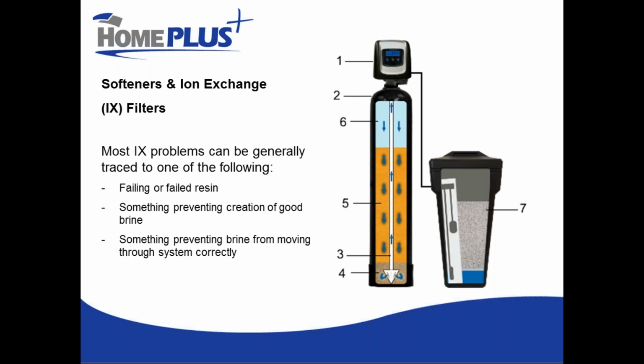So we generally recommend preventative maintenance. Clean your brine tank out once a year and check the operation of your safety float, check the operation of that check ball. And all you have to do to check the operation of that check ball is to tilt it back and forth and you'll hear it moving around in there. But if it's not free and moving, then there could be debris in there because it got dirty in the brine tank and we sucked some debris in there. Does that cover that okay?